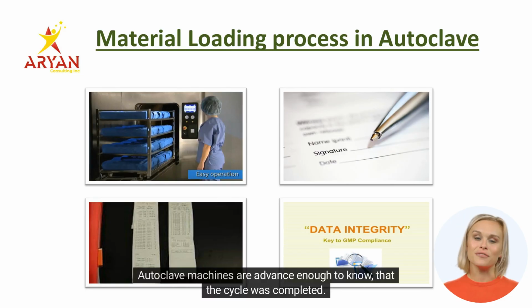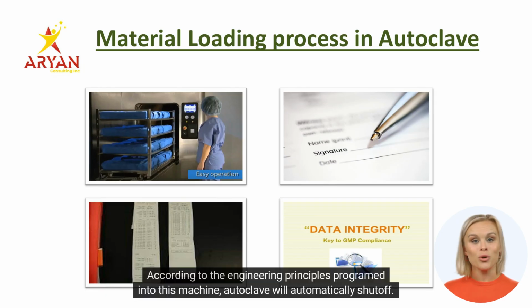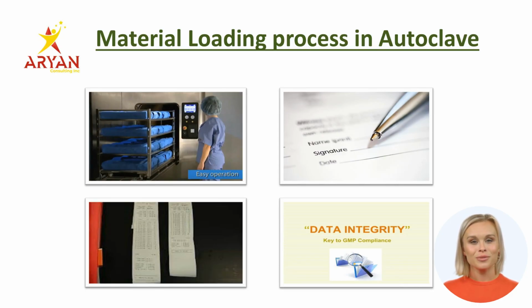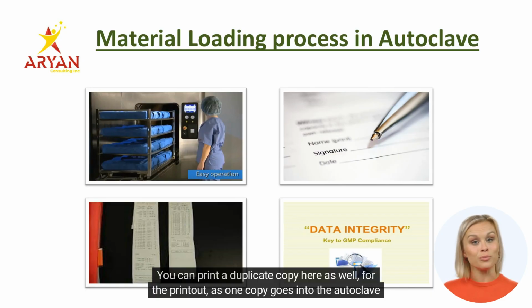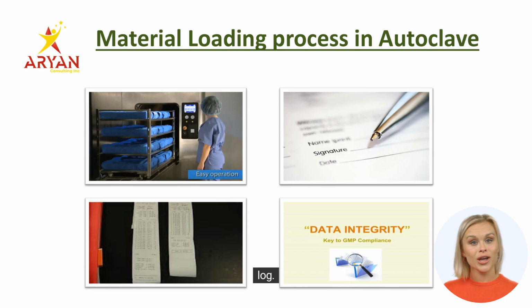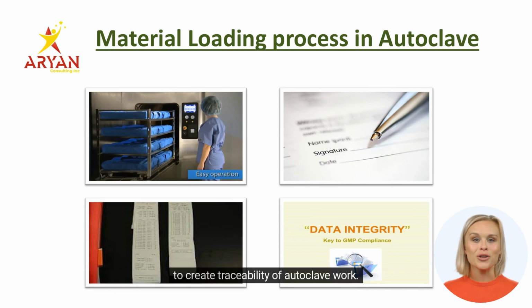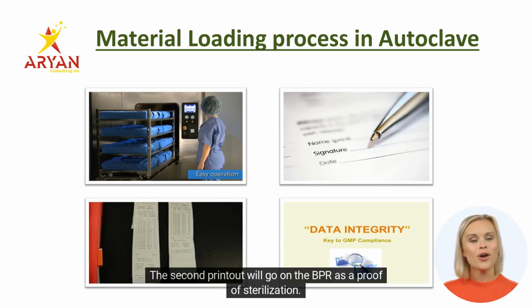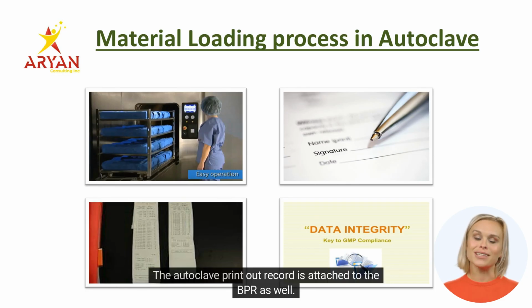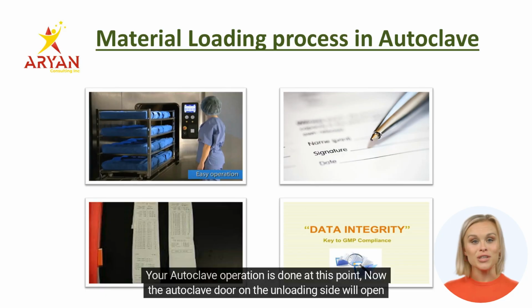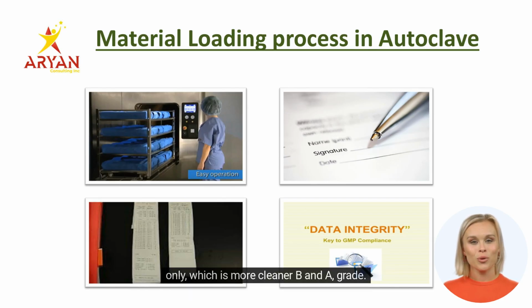Autoclave machines are advanced enough to know that the cycle was completed. According to the engineering principles programmed into this machine, the autoclave will automatically shut off. You can print a duplicate copy of the printout as well, as one copy goes into the autoclave log to create traceability of autoclave work. The second printout will go on the BPR as proof of sterilization. And as you remember, this printout is raw data or metadata. The autoclave printout record is attached to the BPR as well. Your autoclave operation is done at this point. Now the autoclave door on the unloading side will open only, which is the cleaner B and A grade side. Next activities will be performed from there.